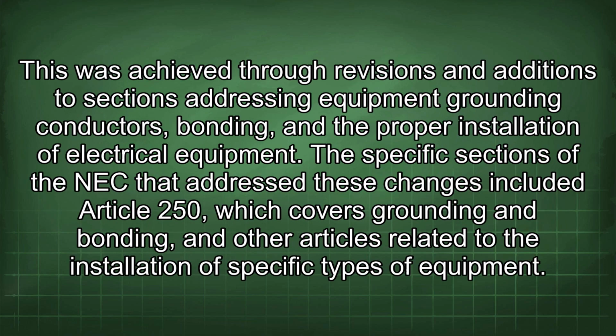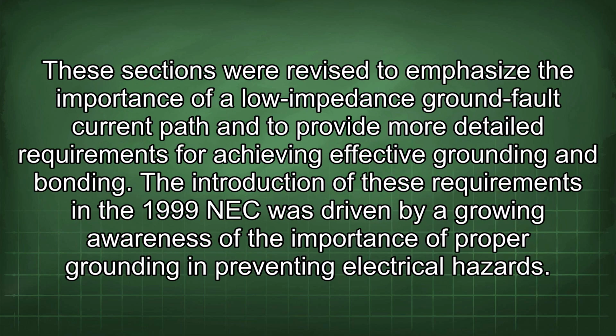This was achieved through revisions and additions to sections addressing equipment grounding conductors, bonding, and the proper installation of electrical equipment. The specific sections of the NEC that addressed these changes included Article 250, which covers grounding and bonding, and other articles related to the installation of specific types of equipment. These sections were revised to emphasize the importance of a low-impedance ground fault current path and to provide more detailed requirements for achieving effective grounding and bonding.